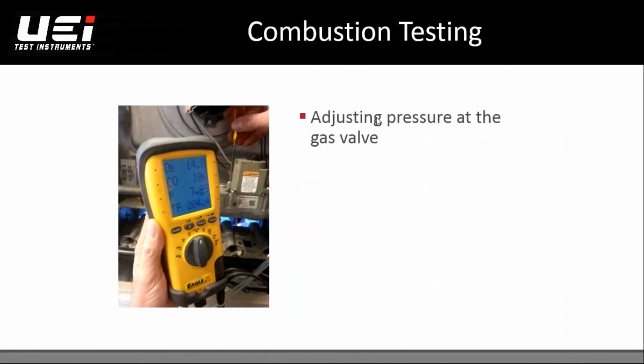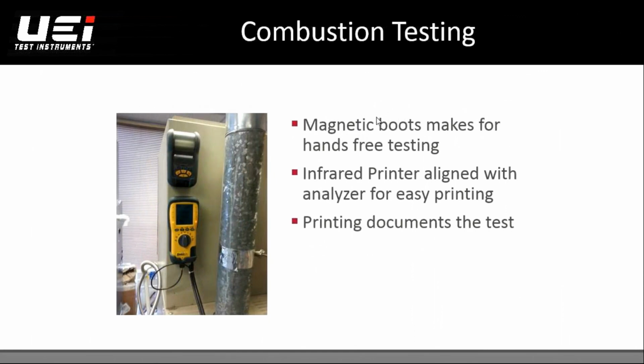We talked about adjusting the pressure at the gas valve, and that's really important. If the gas pressure isn't proper, you're definitely not going to have an efficient boiler or furnace. With a combustion analyzer, especially our C165 which I'll show you in a minute, you'll see your pressure readings and the instantaneous results of what's going out the flue, so you can make adjustments while watching it without unhooking and rehooking things.